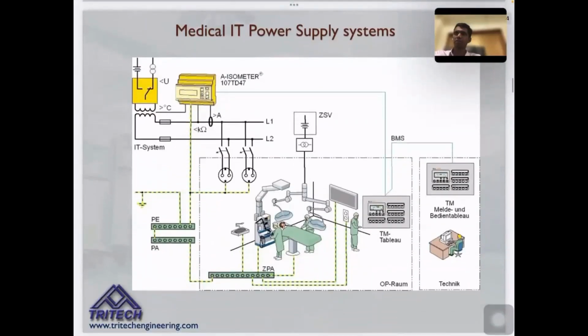And I'm just showing you one of the smaller systems, which is also called the IT system. It's actually the isolated power supply system, also called the medical power supply system. Basically, it's an ungrounded system, so it will not work on a tripping basis. It will work on a power monitoring basis. This is, as per the National Building Code, and in India also we follow that. This is a critical utility for healthcare.